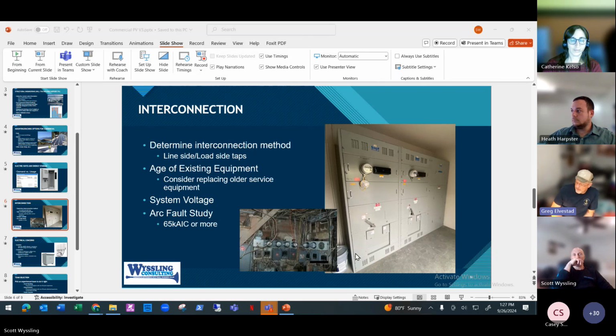Because at the end of the day, we want to make sure we're making a connection that is code compliant, in that we're not modifying a piece of equipment. Although UL is a great organization, we don't want to have to enlist their services to relist a piece of switchboard or any electrical equipment after we've modified it, and there's a risk that they may not even certify it, and we'd have to spend $6,000 to $10,000 for them to come and evaluate it, only to find out that we can't do what we thought we could do. So that's very, very important, to be able to see what's inside door number 1, door number 2, and door number 3.